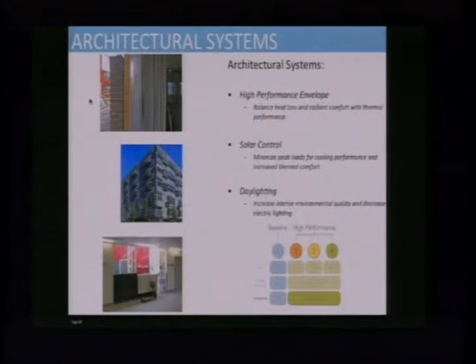So then building mechanical, this is where we realize a lot of the energy savings and where a lot of the energy waste is happening in hospitals today. So in the baseline system, it's really a VAV system. In the patient rooms, it's 6 air changes per hour, overhead mixing system. In the OR and ED and kitchen, it's a higher air change rate. It's the code minimum air change rate. And we chose VAV as the baseline.